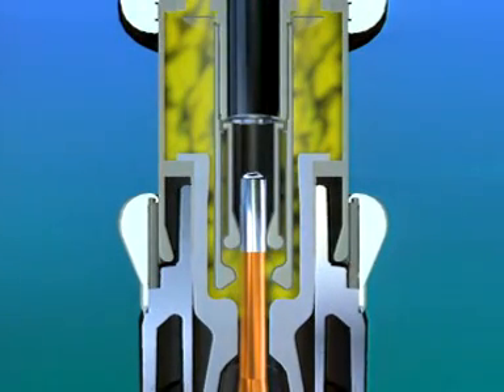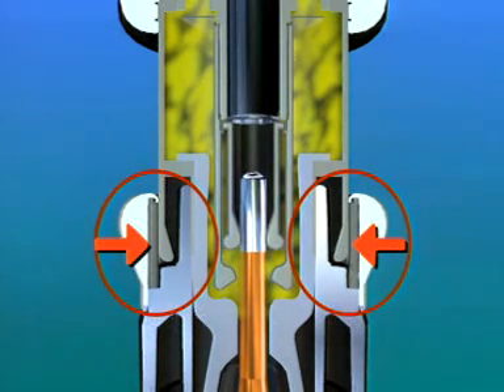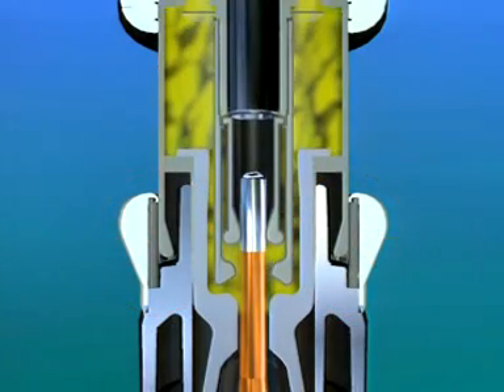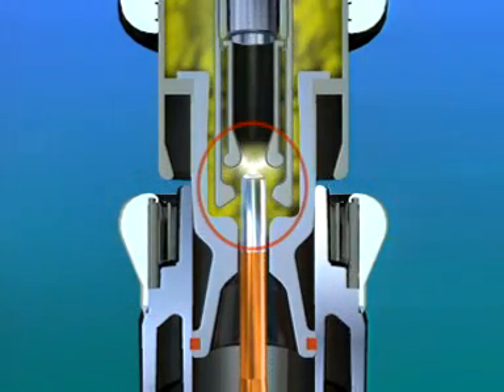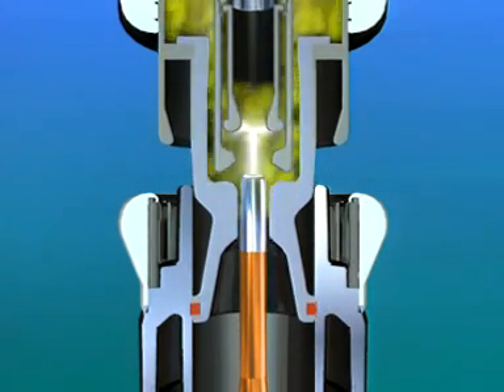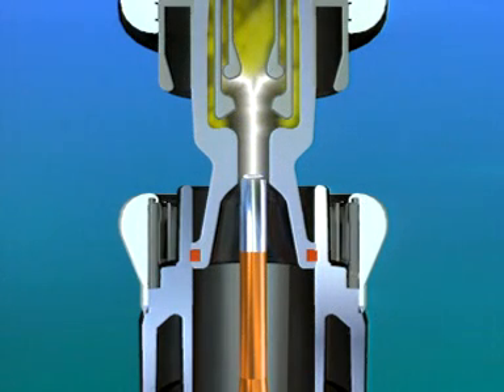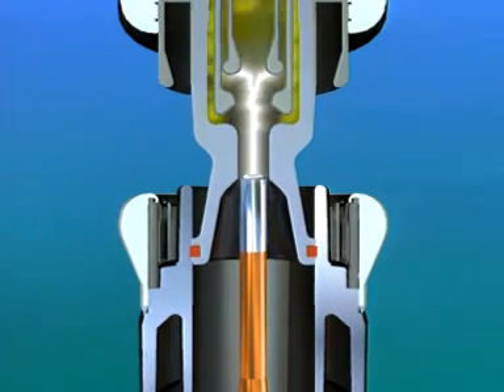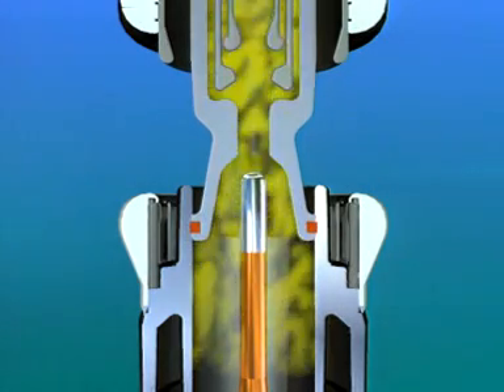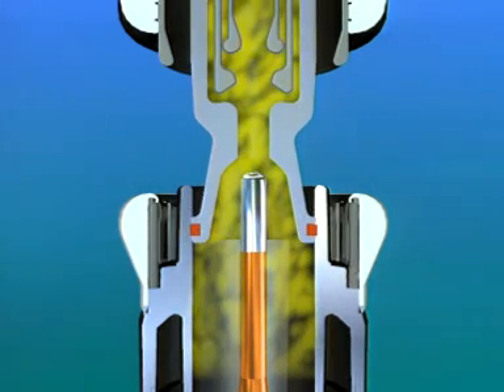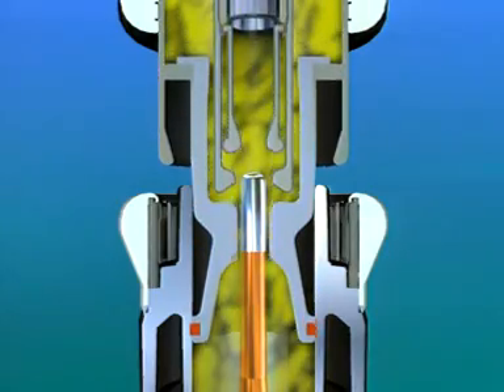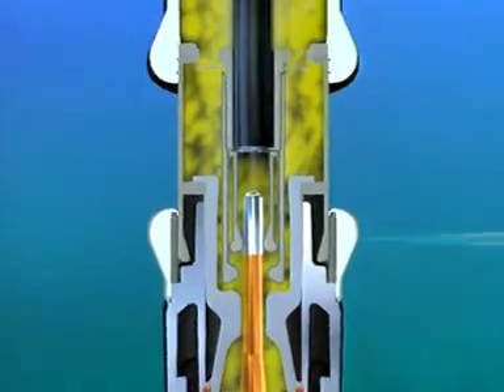The interrupter unit operates in accordance with the self-compression principle. When the circuit breaker is closed, the current flows through the main contact. During the break operation, the arcing contact conducts the current. This prevents erosion on the main contact. An arc is produced on separation of the contacts. It reaches a temperature of up to 20,000 degrees Celsius. This thermal energy increases the pressure of the quenching gas. It flows through the contact cylinder into the breaker gap and quenches the arc in a few milliseconds. The arc's thermal energy reduces the necessary operating energy to the pure motion of the contacts.